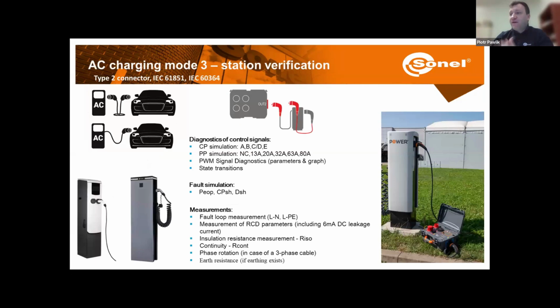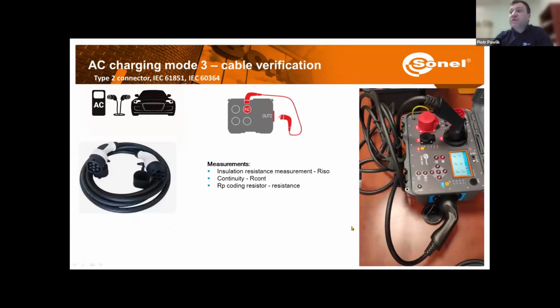Now, as per mode 3, when we have an AC charging station, for the station itself, whether it has a socket or attached cable, we need to measure fault loop impedance and RCD parameters, including DC leakage current above 6 milliamps. We need to check insulation resistance, continuity, phase rotation for the three-phase charging stations, and in case they have their own earthing, we also need to check earth resistance. Diagnostics and fault simulation are just the same as for the cable. But further on for mode 3, in case we have a charging station only with a socket, it will also be good to check the charging cable.